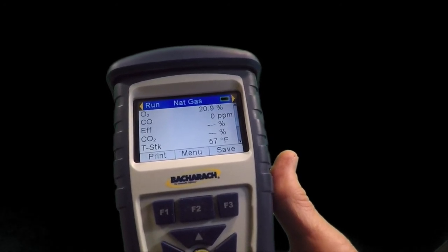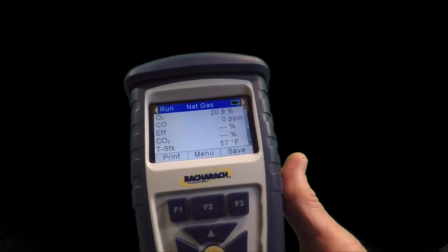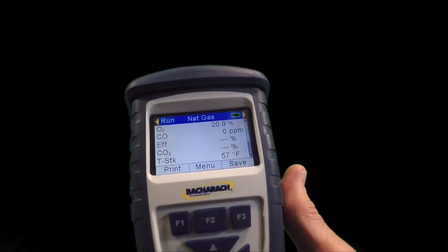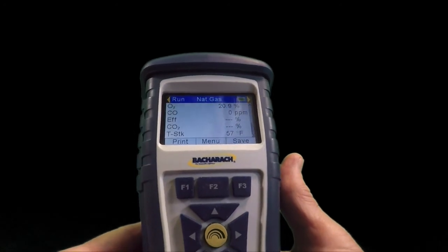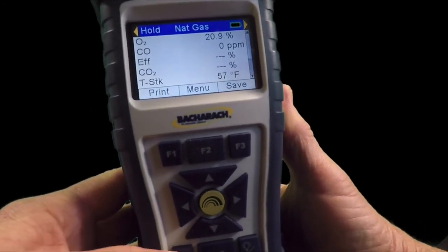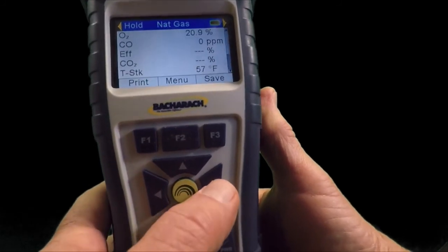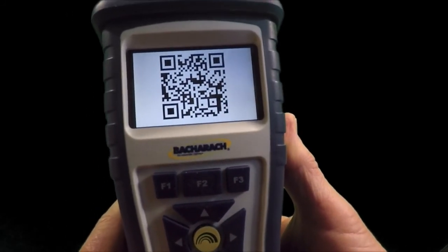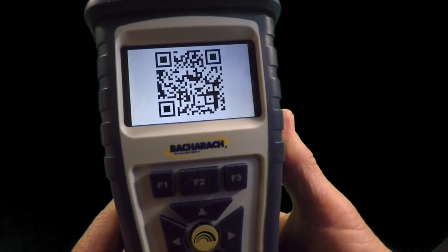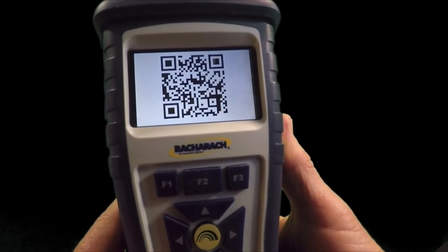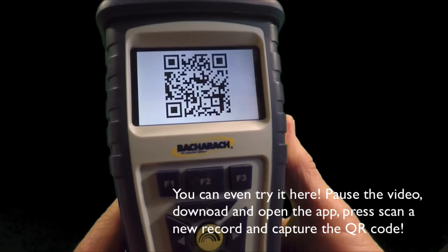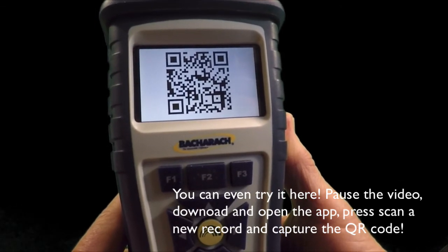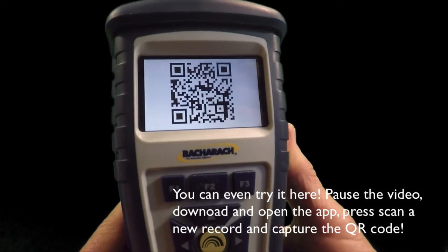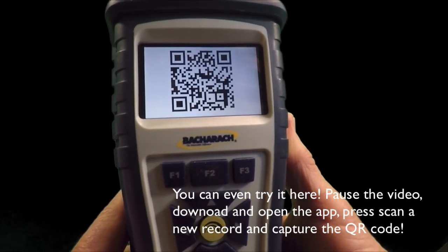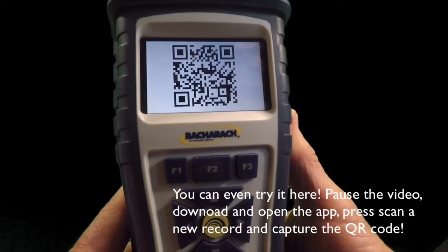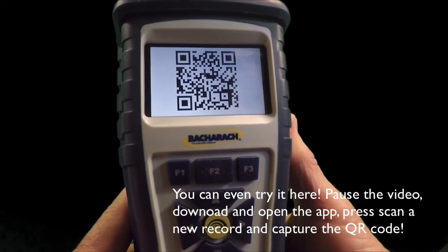This is really, really amazing. I'll cover this in depth on another video. Definitely check it out. You bring up the test results that you want to document. You hit the run hold button to stop the pump. You press the scroll right button and a QR code appears in the display. You open up the Bacharach reporting app on your smartphone and click scan a new record. Hold your phone's camera over the display of the instrument. When it captures the QR code, your phone will ding and a PDF file of the test results will come up on your phone. From there you can email out the test results to your office, the customer, or wherever.